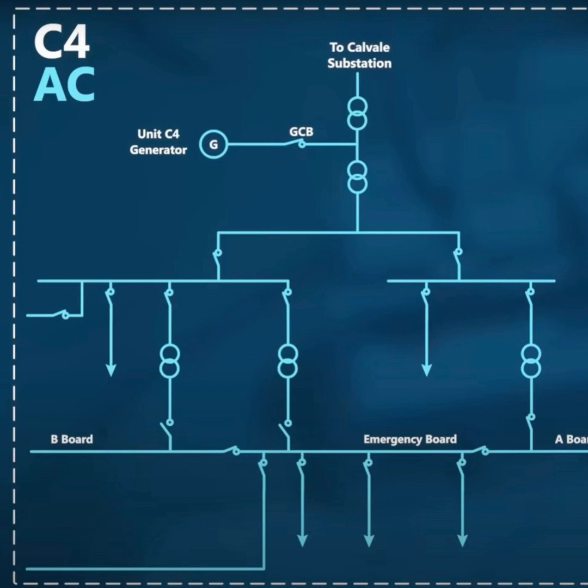However, they are more expensive, and with the modular design of switchboards these days, drawing a straightforward SLD can cause headaches for the designer when they're laying out the board. The really fancy ones I've seen in the past go so far as to have green indicator lamps to show which bus is live, the position of the ACB, with lamp indicators that follow the single line diagram on the switchboard. That said, I haven't seen one of those in years. I suspect that with the prevalence of SCADA systems, a decision that's becoming quite common is to not pay the extra for the SLD mimic overlay and to go with the cheaper design, relying on SCADA for remote indication.